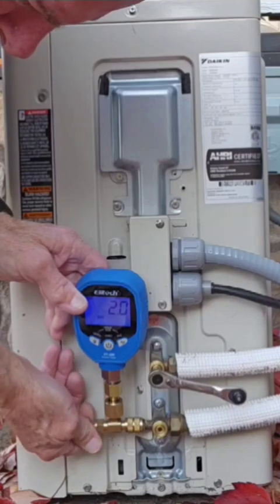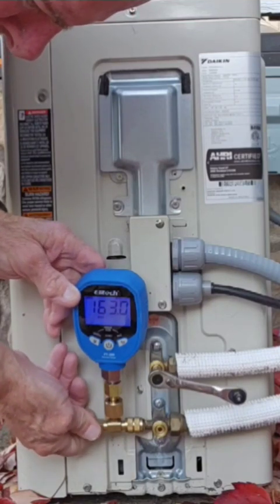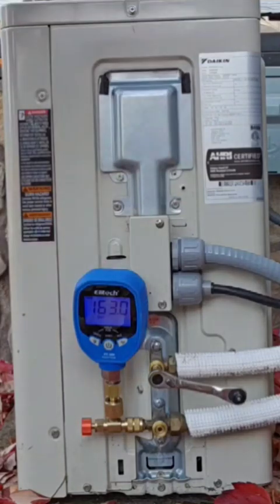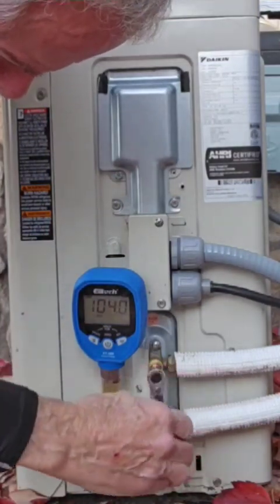We're going to go ahead and perform a pump-down service on this system. We'll push the valve core all the way in with the charging valve, and that'll read our pressure of the system right now. It's 163 psi. It's 57 degrees Fahrenheit outside, so that's perfect for R410A.